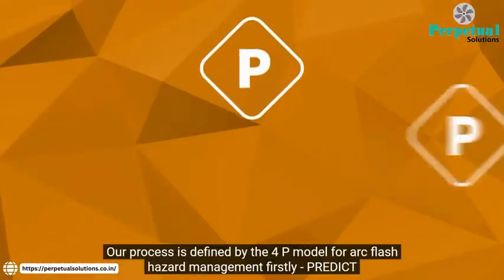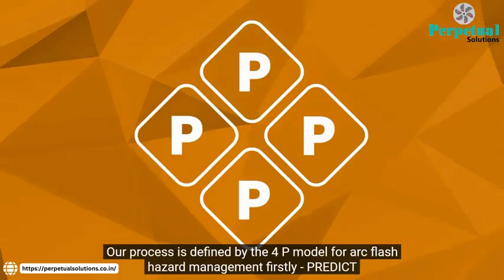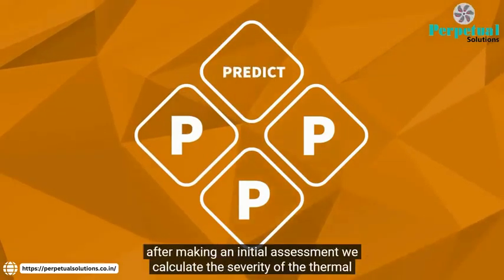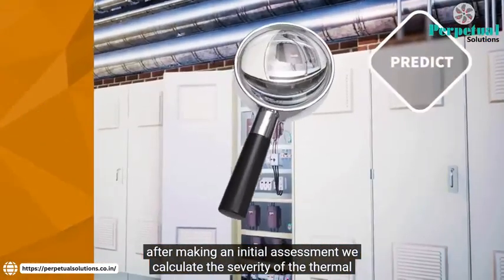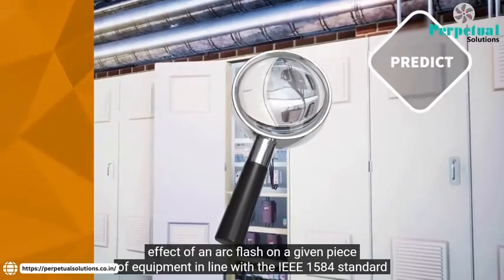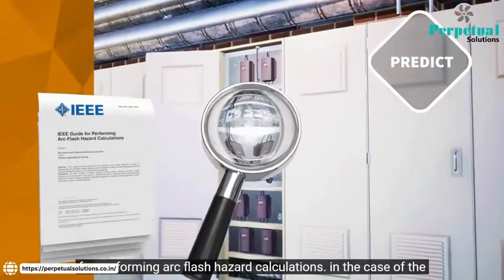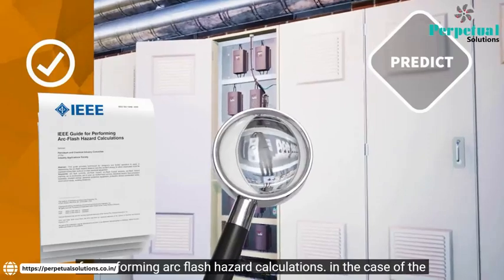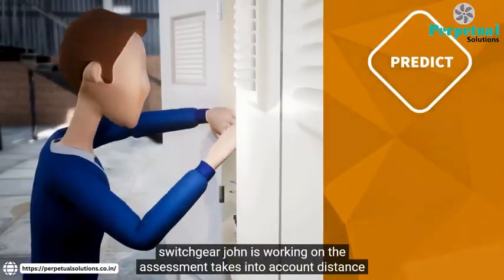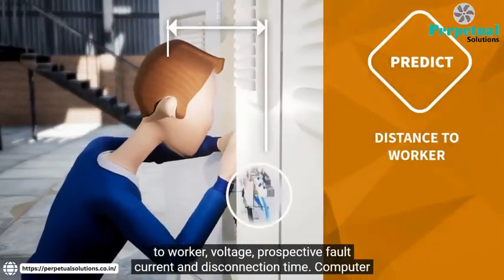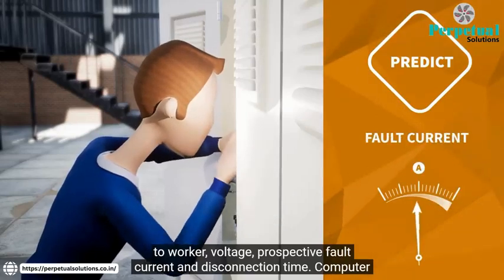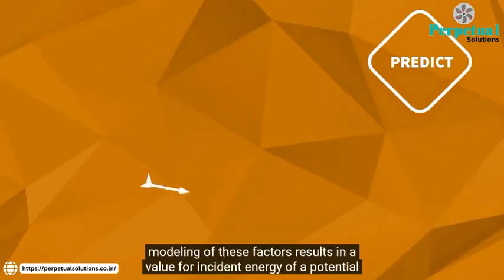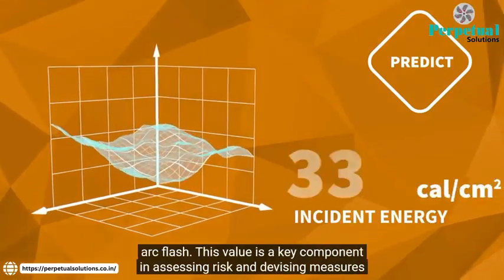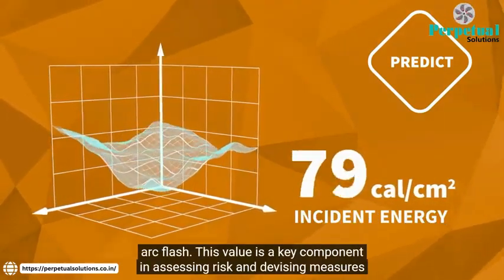Our process is defined by the 4P model for arc flash hazard management. Firstly, predict. After making an initial assessment, we calculate the severity of the thermal effect of an arc flash on a given piece of equipment, in line with the IEEE 1584 standard for performing arc flash hazard calculations. In the case of the switchgear John is working on, the assessment takes into account distance to worker, voltage, prospective fault current, and disconnection time. Computer modeling of these factors results in a value for incident energy of a potential arc flash. This value is a key component in assessing risk and devising measures to be taken to prevent.